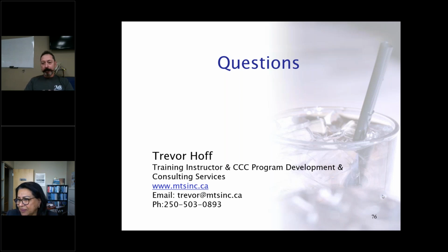Unfortunately. Okay. Actually, I had this question for you yesterday when we were practicing. Any significant difference between the AWWA cross connection control manual M14 and the CSA B64.10? Yes, excellent question. The AWWA M14 still is referenced in the appendix of the plumbing code as considered good practice for the installation of backflow preventers for fire sprinkler systems. So that's where it shows up in the plumbing code. It references fire sprinkler systems, and M14 is a good practice.